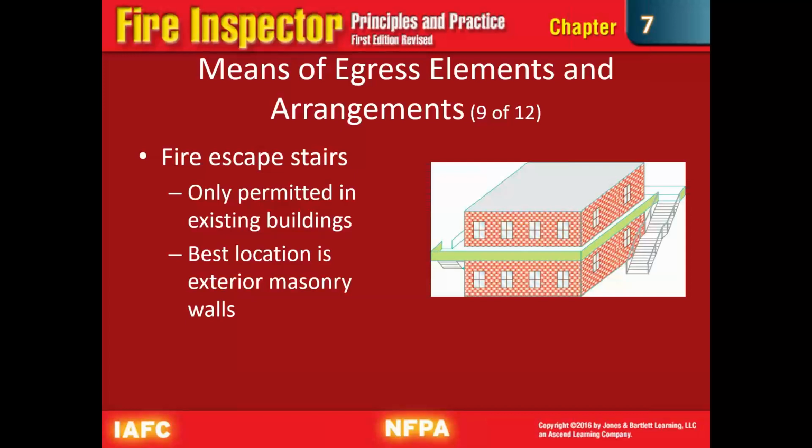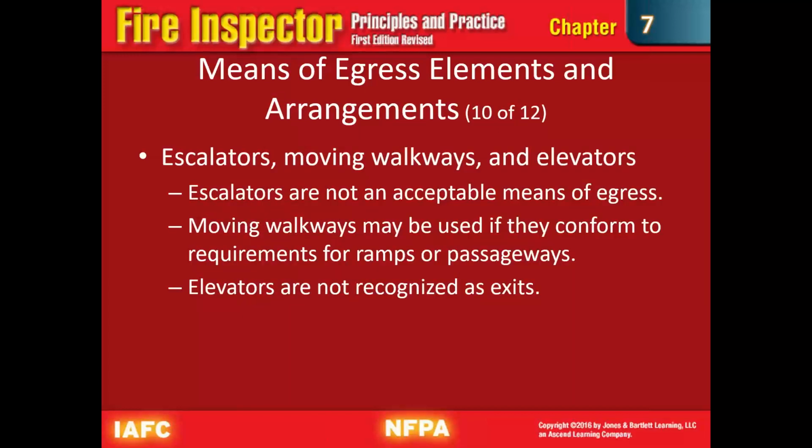escape stairs. I've seen it in a few different places, like some old school buildings, where they had put escape stairs in place. And it has in here your best location for exteriors, masonry walls, escalators, moving walkways, and elevators. Escalators are not an acceptable means of egress. Moving walkways may be used if they conform to the requirements for ramps and/or passageways, and elevators are not recognized as exits.